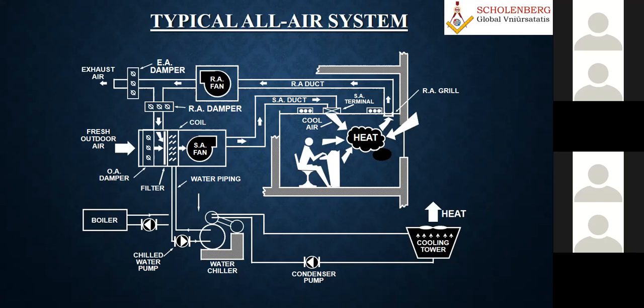But again, when you come to the ducting side, we are again doing it zone-wise. Single zone-wise also, because we have a common plenum. From the common plenum, we have different kinds of branch ducts, and on the branch ducts we also have different kinds of collars, and then various zones also. Various zones have to be maintained with different temperatures, different controls are required, but we may be using only one air handling unit. So this is what, as a design engineer, you decide during the pre-stage itself, depending upon the process.